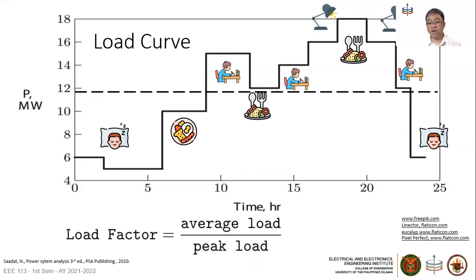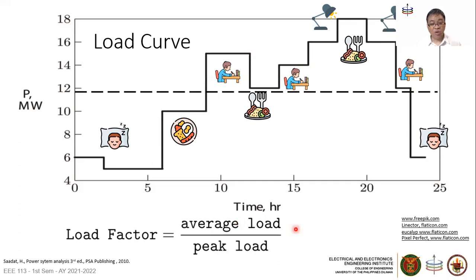The trouble is that electrical equipment must be rated for the 18 megawatt peak demand, yet throughout the day electricity use is much less, so equipment is generally underutilized. The ideal case is to flatten this curve so that the peak load is very close to the average load, making the load factor approach one. We can only achieve that with a large community having varying activities and behaviors — so a large interconnected network can help flatten the load curve.